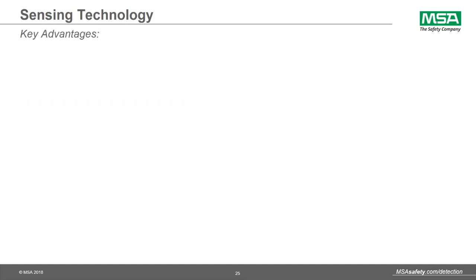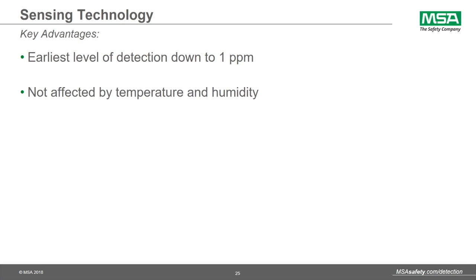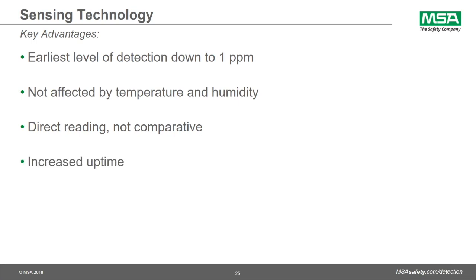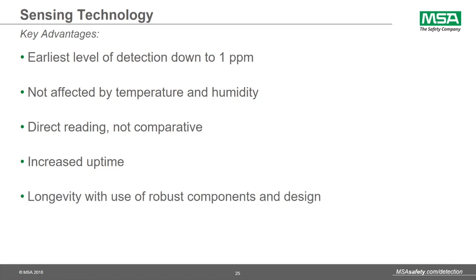So I'm going to go ahead and go through some of the key advantages of photoacoustic infrared. Like we mentioned earlier, it gets down to that low level detection of 1 part per million. It's not affected by temperature and humidity fluctuations, and it's direct reading, not comparative. You have increased uptime because we're not taking the monitor offline for re-zeroing. And you get the longevity because we use very robust components and the overall design of photoacoustic gives you a longer life.